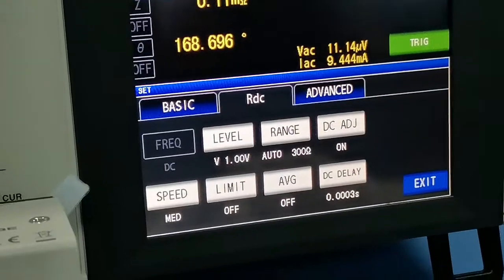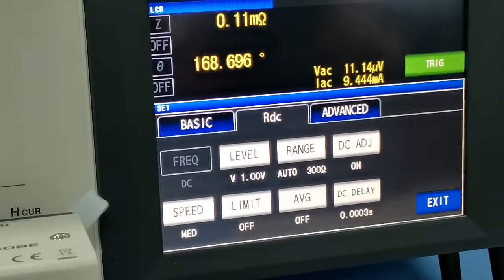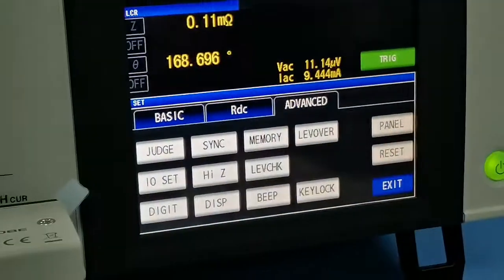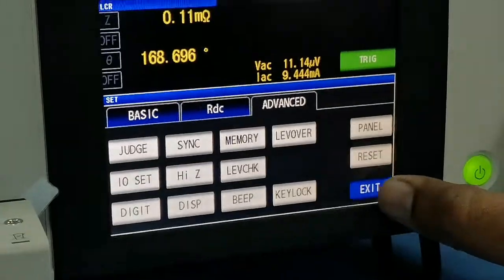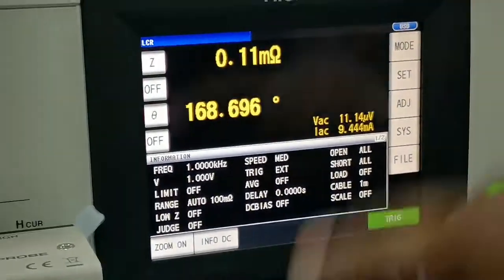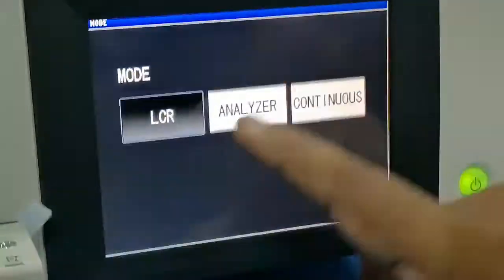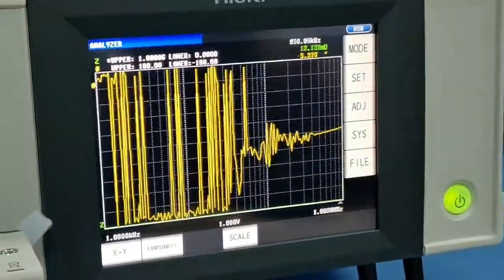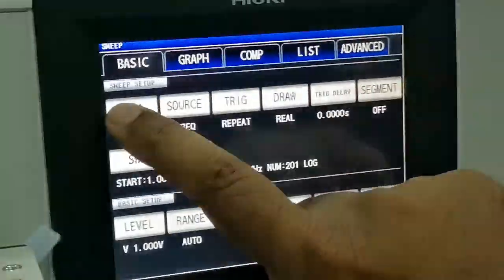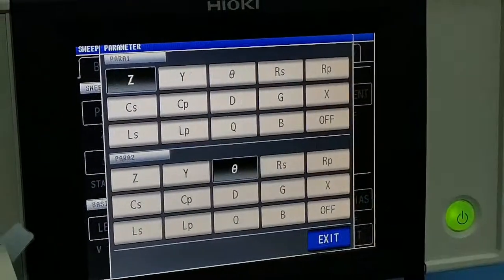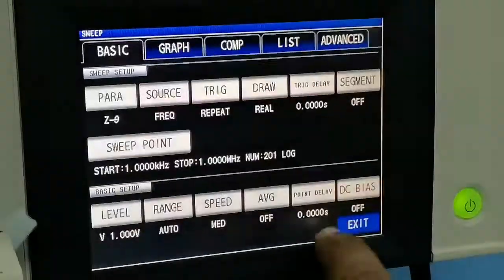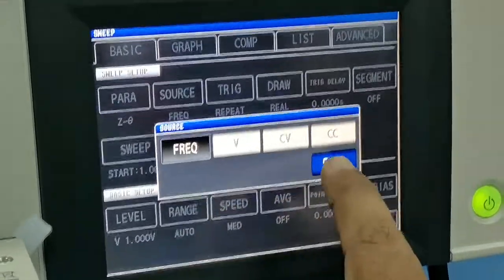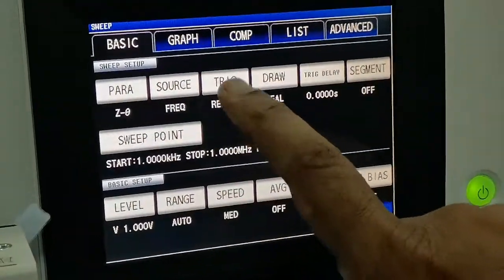This is for the Rdc mode — you can select the voltage and also the DC voltage, and also speed, limit, and average. This is for the advanced one. So this is for the LCR mode. This is the analyzer mode — in analyzer mode you need to do the settings. Same thing, you can set the parameter which parameter you test, then with your source you can put your frequency or voltage.